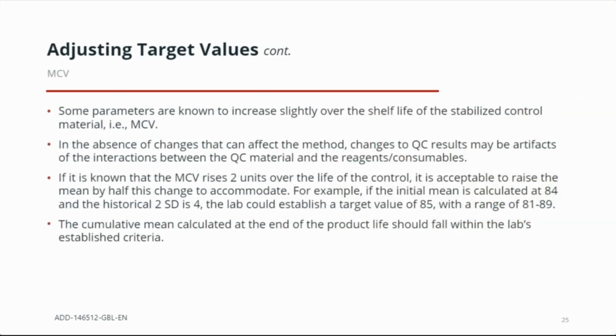We know that some parameters are known to increase slightly over the shelf life of the stabilized QC material, and a good example of this is mean cell volume. In the absence of changes that can affect the method, changes to QC results may be artifacts of that interaction between the QC material and our reagents or consumables. As a great example of when we can adjust target values, we likely have historical data that shows, as an example, a 2-unit MCV rise over the life of the control. Once we have that data, it's acceptable to raise that mean by half of this change to accommodate.